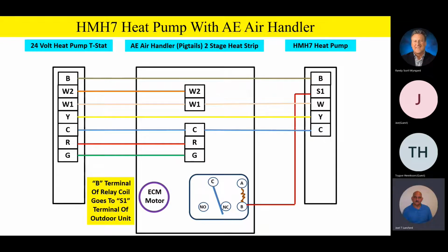When we have reduced airflow, we're going to energize that coil, and we'll show you how that works in a little bit. The other side of that coil of the relay, we're using A terminal in this example. The other side of that coil goes to 24-volt common. So here's the idea: when the outdoor unit sends that 24-volt signal on S1, it's going to change, or click, that relay, or energize that relay.